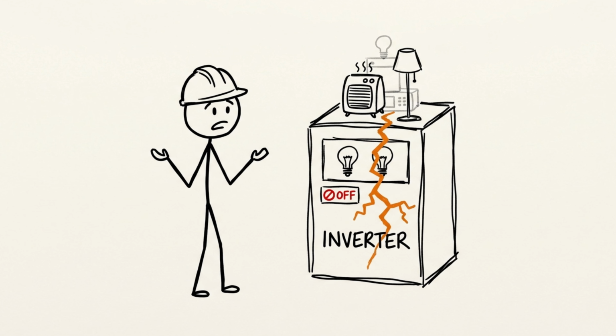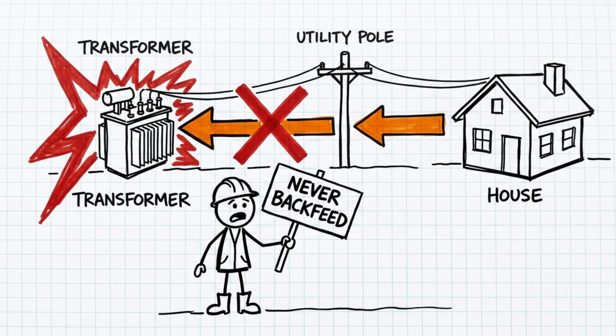Failure 1. The silent overload. Symptom: the inverter shuts down mid-outage for no obvious reason. Actual cause: the simultaneous connected load crept above the inverter's continuous rating. Failure 2. The backfeed ghost. Symptom: utility line workers or neighbors report shocks or strange readings on lines that should be dead. Actual cause: a bypassed or missing transfer switch lets backup power flow backward through the service entrance and into the neighborhood step-down transformer, multiplying household voltage back up to thousands of volts.